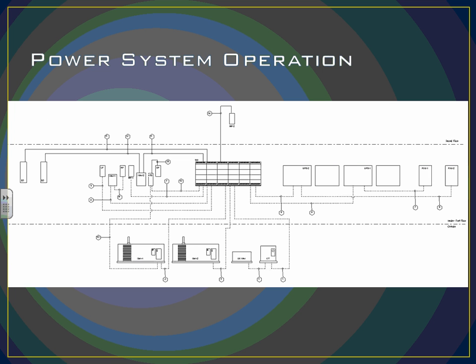For our power system, the way that we started was power coming in, and it's kind of hard to see here, this is our utility transformer here in our CT cabinet. Normal power you see is running back into our switchgear, and then from there, that power is distributed to other transformers and other panels. These are our 2 UPSs and our PDUs that are both serving our data center. And then on this side, a little bit harder to see, this is our ATS right here, and the emergency power panel. That is fed directly from the generator for emergency power systems.